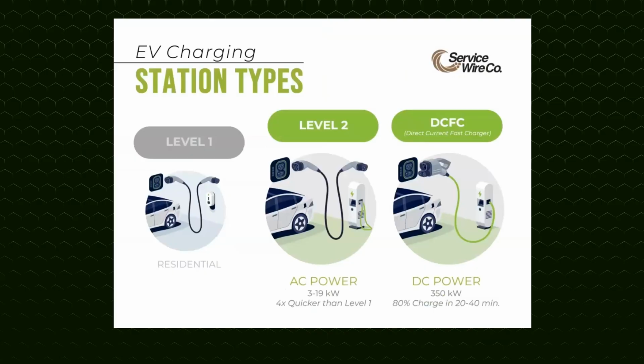But before we jump into low voltage wire and cable solutions, let's review the types of EV charging station projects we can capture. For this discussion, we are going to focus on level 2 and supercharged commercial stations. Level 1 chargers are those typically found in residential settings. Level 2 chargers operate at 208 to 240 volt, 30 amp, and output anywhere from 3 kilowatt to 19 kilowatt of AC power. That's about 19 to 40 miles of range per hour, and these charge about 4 to 5 times quicker than a level 1 charger.